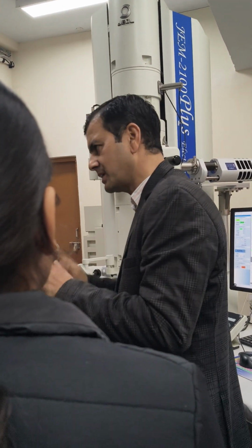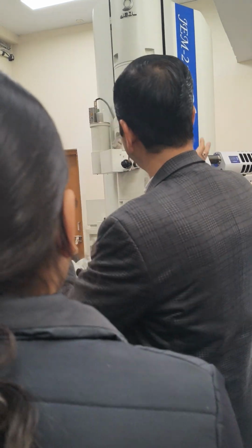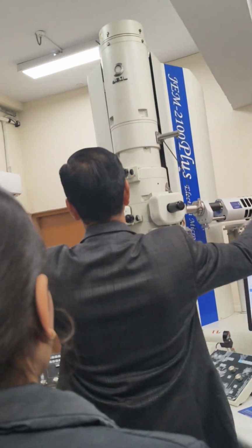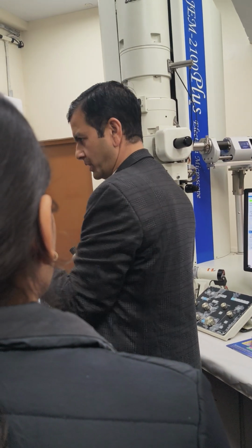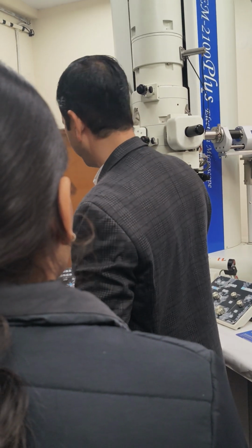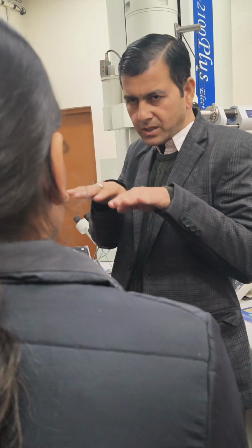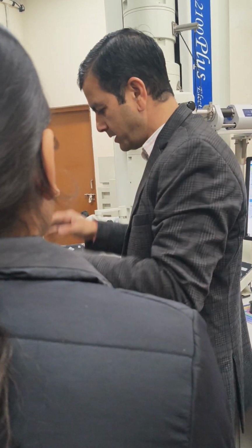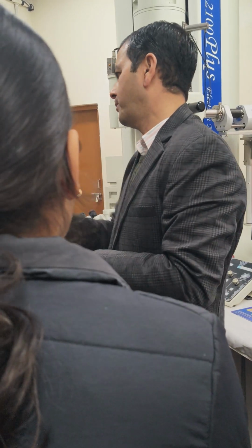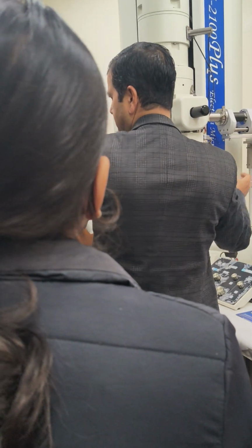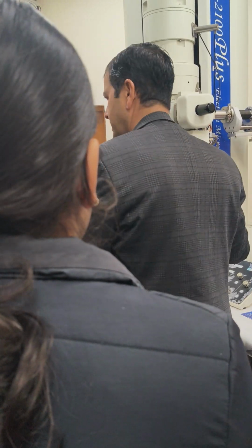The fundamental principle is the same, everything is the same. Layout-wise, many times you find some are bigger. If you need 300 kV field emission or 200 kV, it has a bigger diameter because it needs more isolation from the external environment. It cannot tolerate much vibration, because when we do high resolution imaging, tapping strongly or movement outside will disturb the image. Due to that, a 300 kV or bigger TEM is broader.